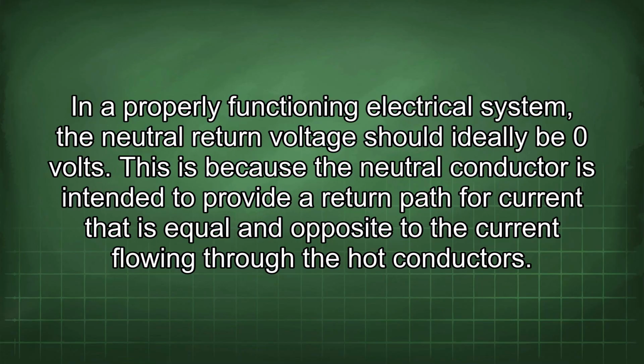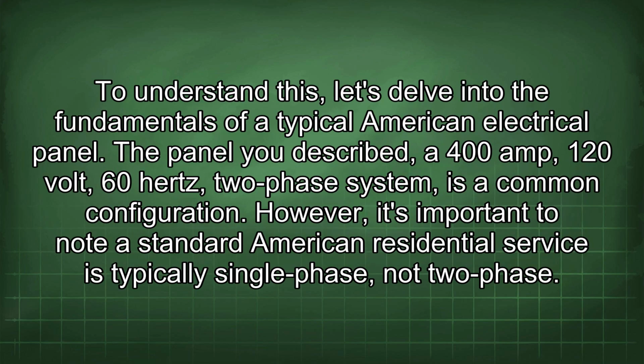In a properly functioning electrical system, the neutral return voltage should ideally be 0 volts. This is because the neutral conductor is intended to provide a return path for current that is equal and opposite to the current flowing through the hot conductors. To understand this, let's delve into the fundamentals of a typical American electrical panel.